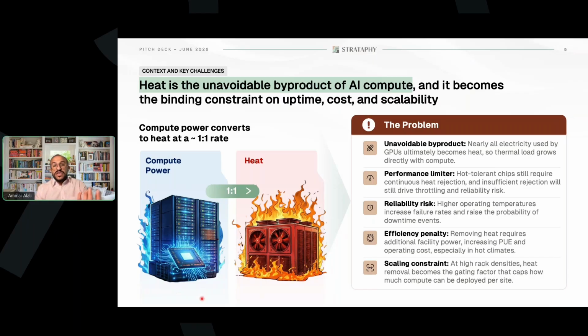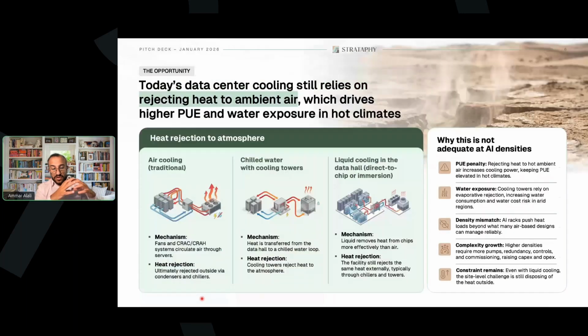So how do they mitigate this issue today? Today, the cooling solution for virtually all data centers really trickles down to three types, and the first type has different variations. The first one is air-based cooling. Air-based cooling could be an air chiller, a package unit, or a dry cooler. A dry cooler does not have mechanical cooling parts.